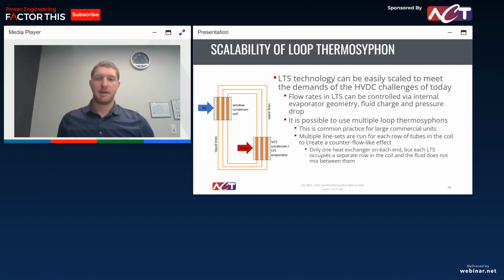So getting back to that scalability, loop thermosyphon can be easily scaled. We've had loop thermosyphons that do 100 kilowatts of power dissipation. It really comes down to how you design the internal geometry of the evaporator, putting in the correct fluid charge, and calculating that pressure drop. One thing we've done at times is multiple loop thermosyphons, so we can use multiple line sets. Each of those is basically at a different saturation temperature, and so you can step up your heat dissipation in multiple line sets, and you can get much greater heat transfer in that way and do a lot more power.